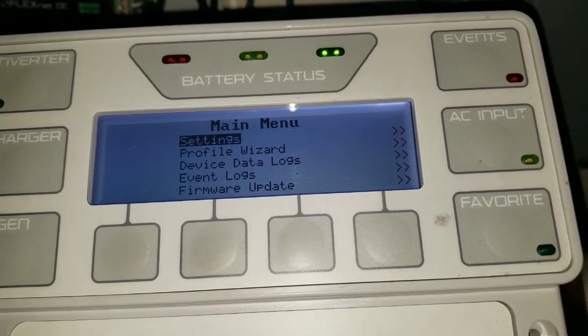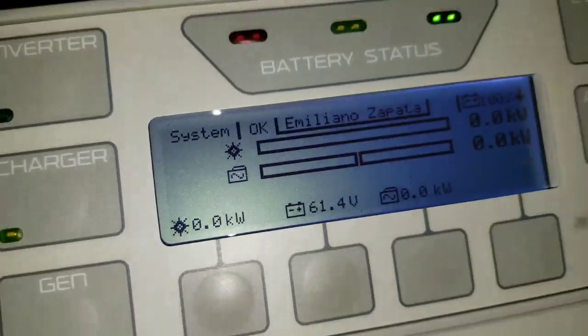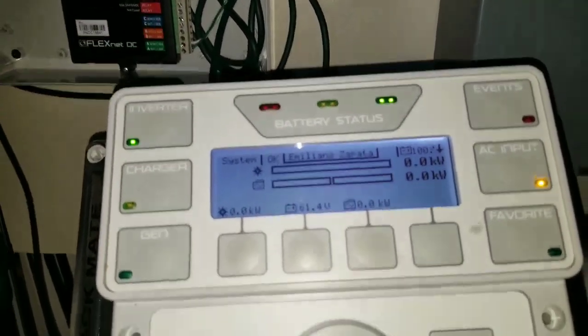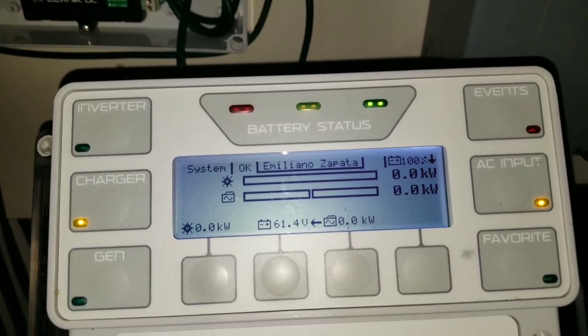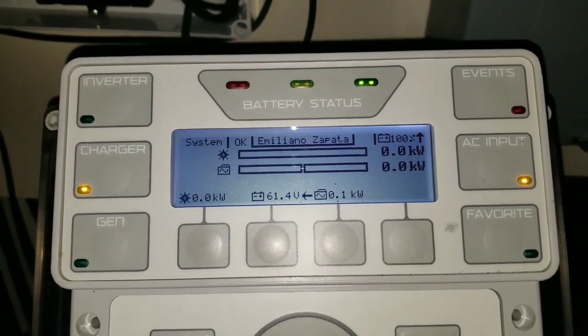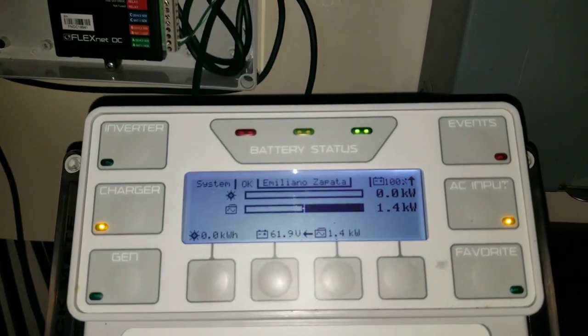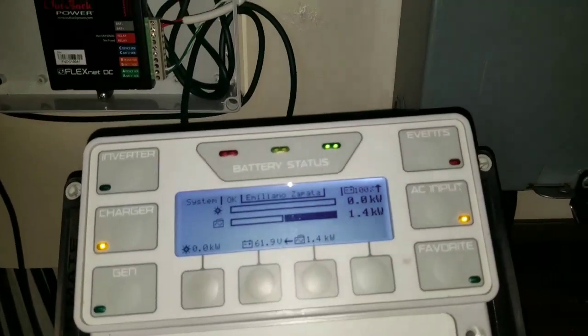Let's go back and turn the AC on to see how this thing charges. AC power is now on - you can see the AC indicator flashing. We're going to be charging the batteries to replace whatever the meter was showing us: 26.6 amps back to the batteries. We're putting in 1.4 kilowatts of charging. After I clean up everything, I can come back and show you guys how the monitoring works.